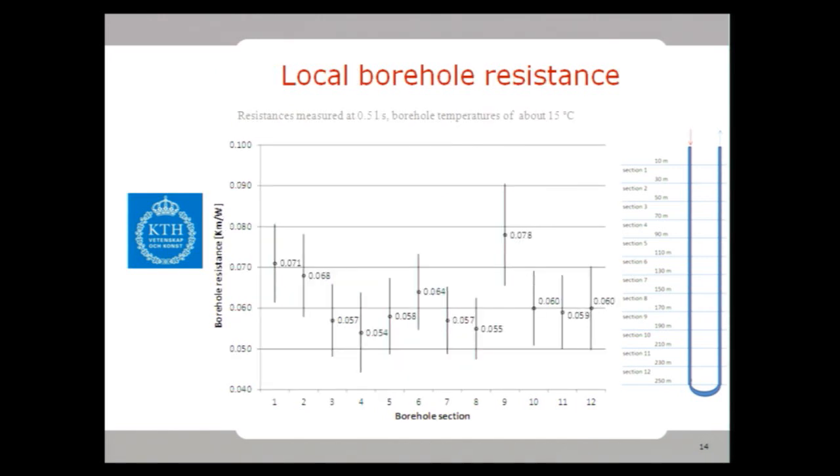The borehole thermal resistance found at each section is presented here, and you can see some slight variations as well, possibly due to some pipe shifting position inside the borehole. And these are measured for this volumetric flow rate and at this temperature level.